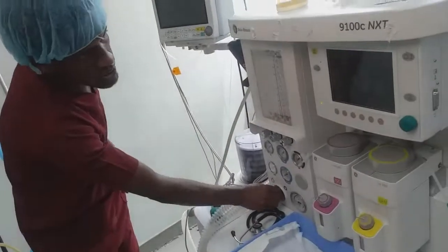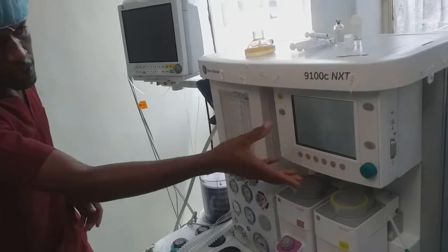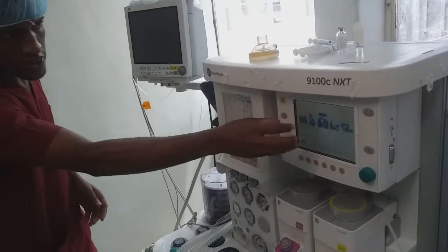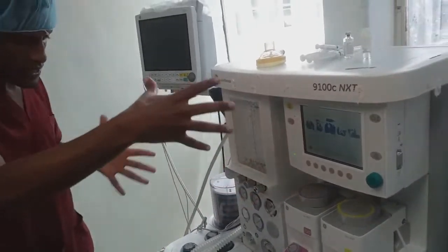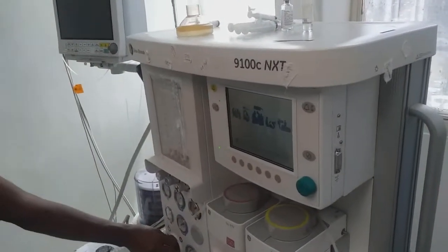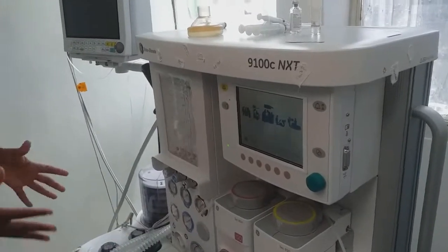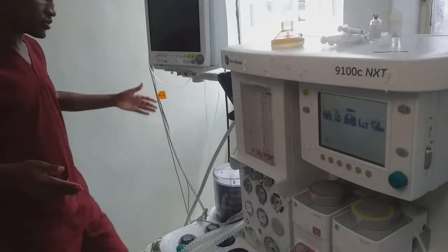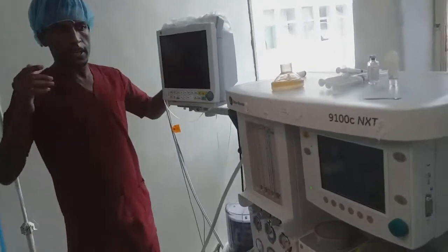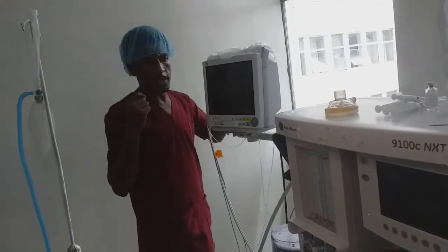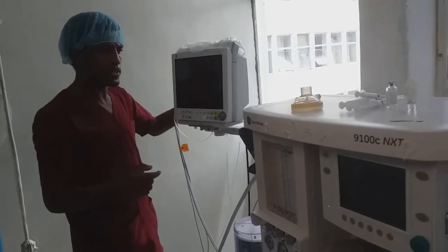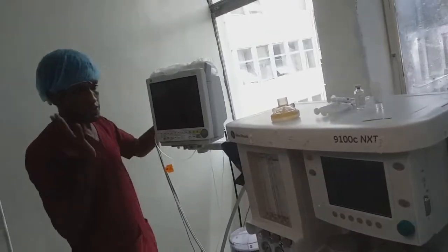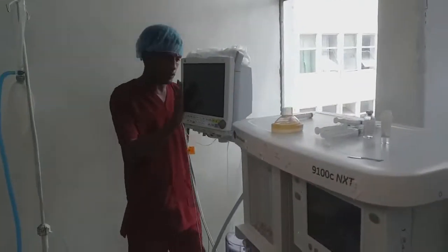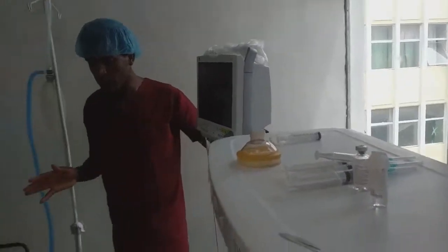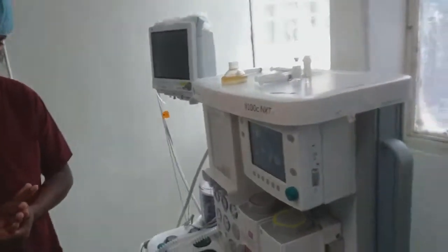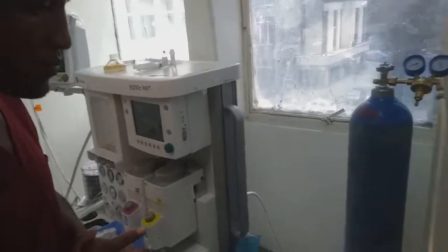You can also check whether the anesthesia machine is charged or not. This indicates that there is a charge, so you can close it. So the electrical circuit should be checked, appropriately plugged in, and switched on, and adequate battery backup is mandatory every day. Now I'm going to check the pneumatic component of the anesthesia machine.